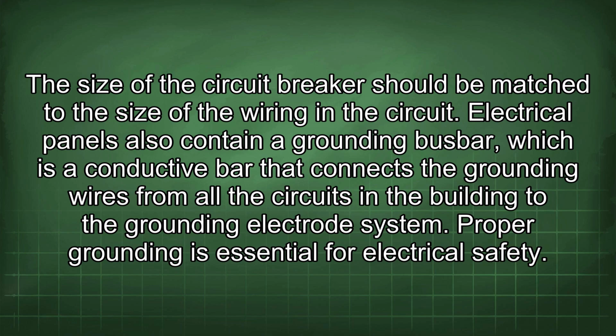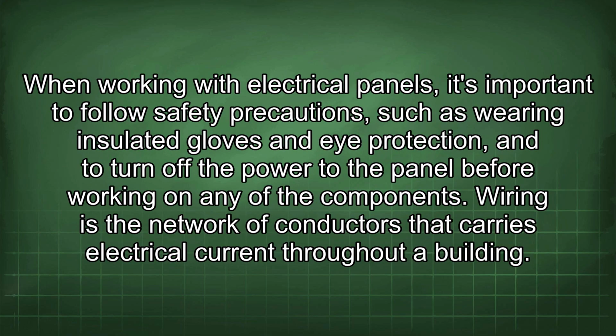Electrical panels also contain a grounding busbar, which is a conductive bar that connects the grounding wires from all the circuits in the building to the grounding electrode system. Proper grounding is essential for electrical safety. When working with electrical panels, it's important to follow safety precautions such as wearing insulated gloves and eye protection, and to turn off the power to the panel before working on any of the components.